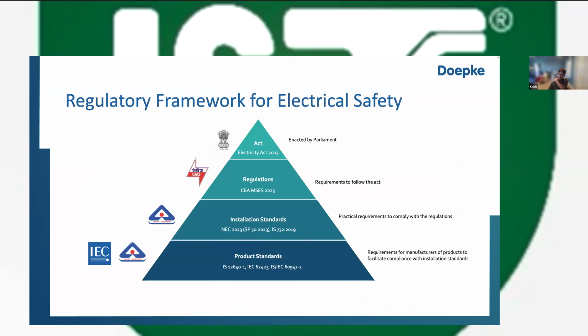And then we have installation standards, which are required to be followed as per the regulations. And then we have product standards, which are mentioned in installation standards. So product standards say you shall select a product conforming to this standard. So the Electricity Act is enacted by Parliament. The CEA regulations, measures relating to safety and electric supply 2023, has now been amended in 2026 as well. Very recent. So that doesn't really affect the elevator industry so far. Then we have the installation standards as well. In India, we have the National Electrical Code of India, SP 30/2023. And we have IS 732, the code of practice for wiring installation. And then there are product standards like IS 12640 Part 1, IS 60947 Part 2, etc.